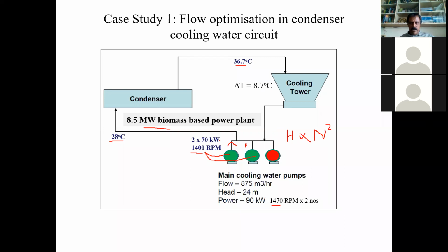Now what we're going to do is reduce this RPM further. In the second case, we reduce the RPM to get a delta T of 10 degrees. So we make the necessary reduction in RPM. We find that we have got this 27.9, 37 points, so a 10 degree delta T we have achieved. Corresponding to that, the RPM is 1300. So 1300 RPM, and the power here is only 55 kilowatt.